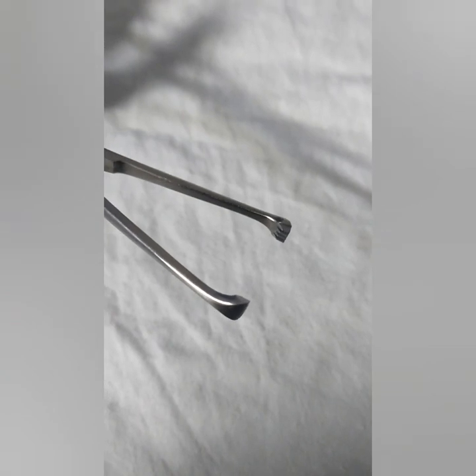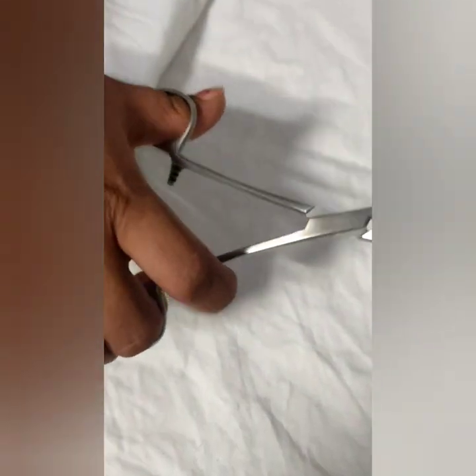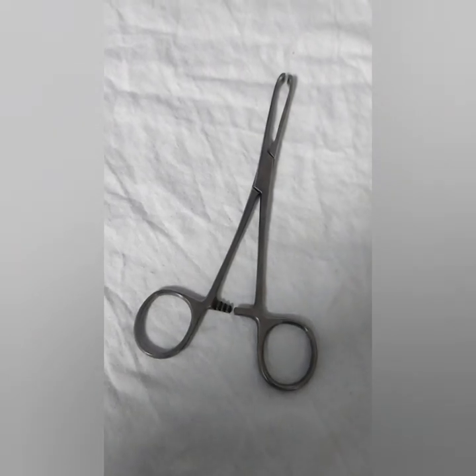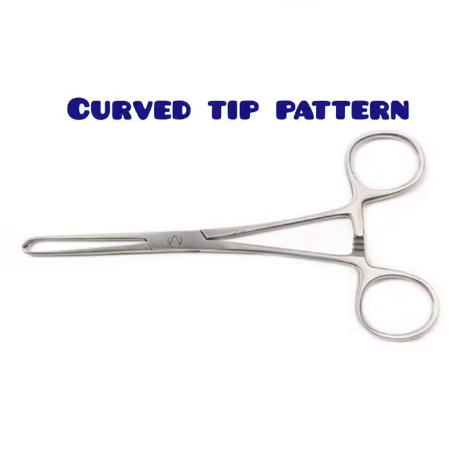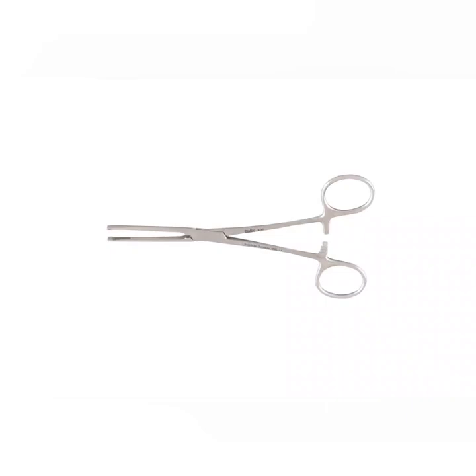Parts of Allis tissue forceps include curved or angulated tips provided with fine and sharp interlocking teeth, blades, box lock, ratchet, shank, and finger rings. The Allis forceps have a ratchet locking mechanism. The terminal end of the blades bears short teeth with grooves in between, so that when the two blades meet, one tooth of the blade fits in the groove of the other. The forceps are available in two patterns: curved tip and straight tip.